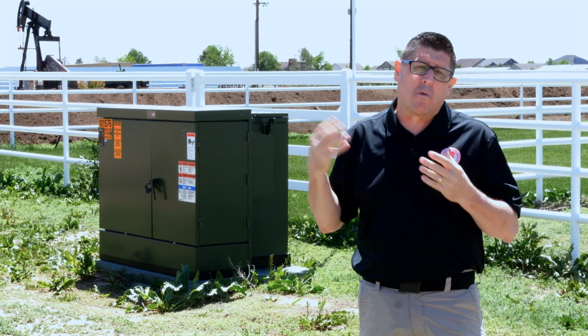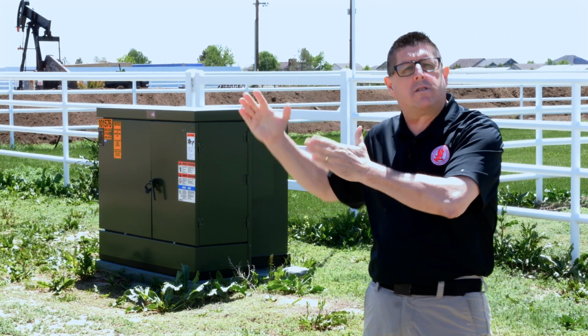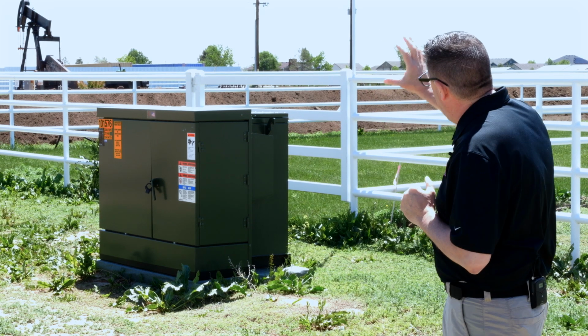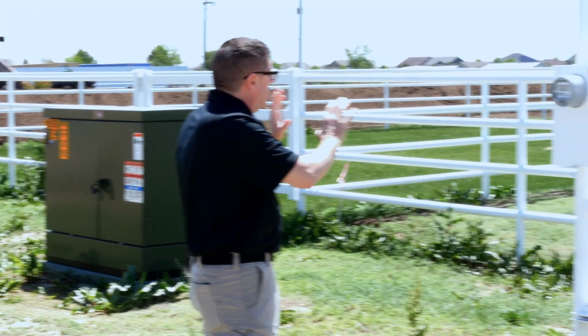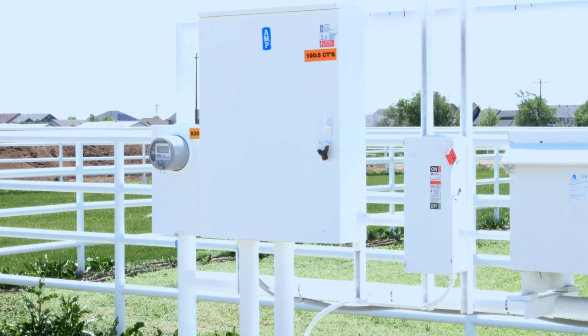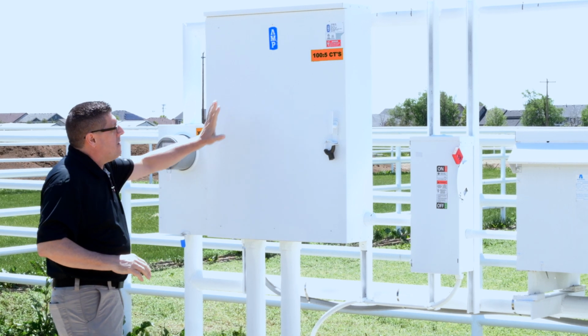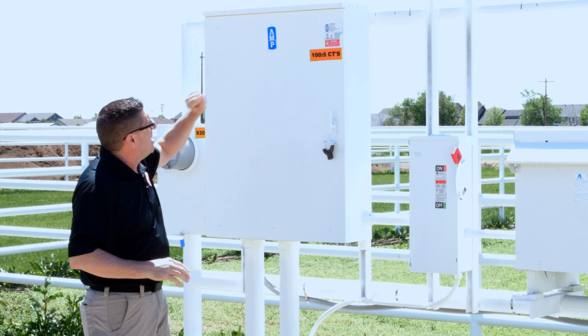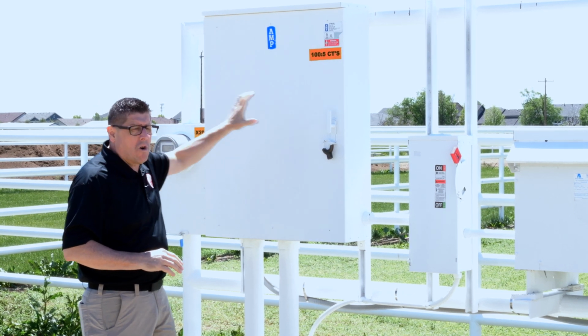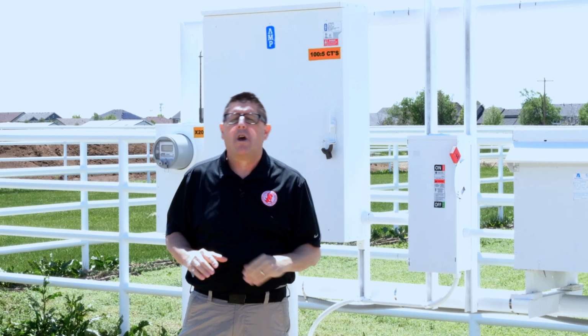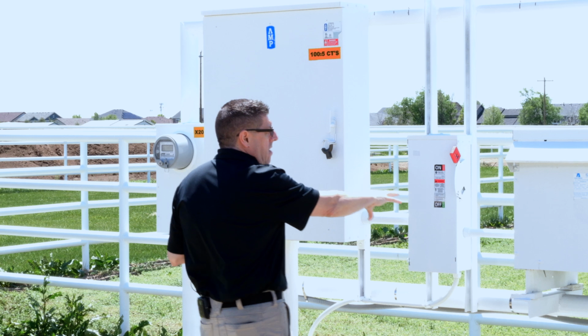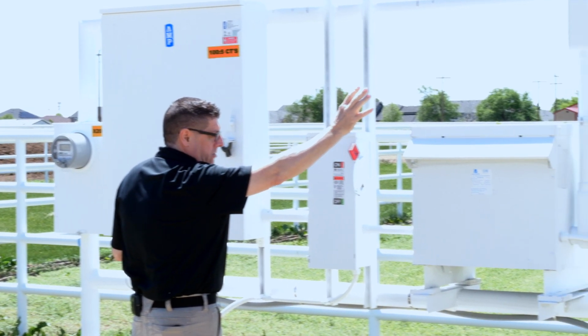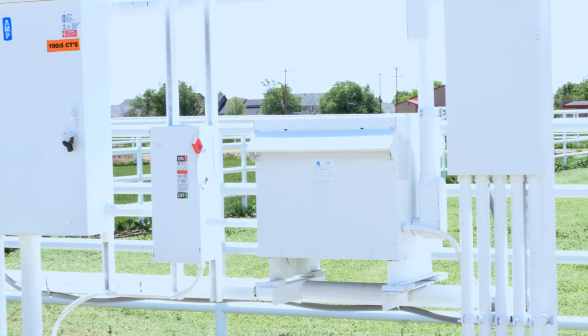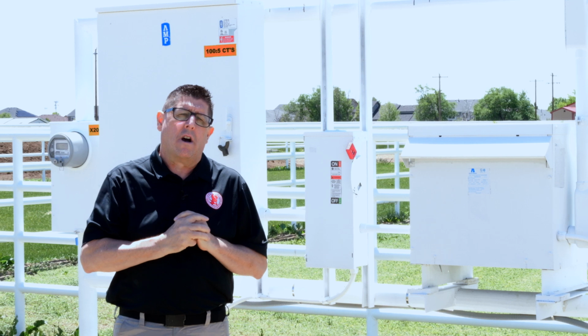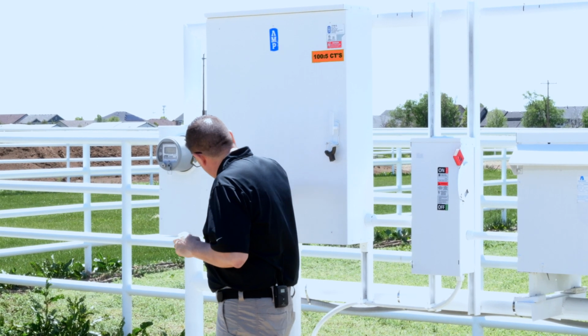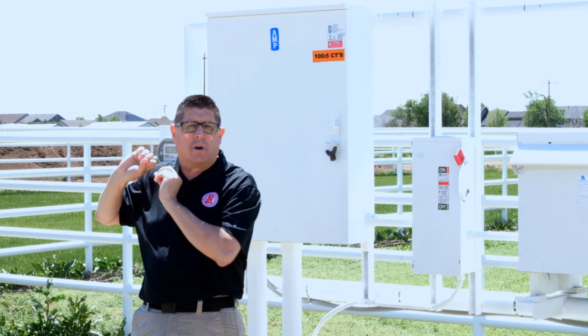But at least identifying where that service is coming from will help you identify how things maneuver and migrate through the property. So we go from that utility to over my left shoulder to where all of this distribution is located. We've got a meter socket here. We've got a utility CT panel here. This is rated at 600 volts, 400 amps, and then this is being distributed through the rest of the campus. We've got a disconnect here, a transformer here, and we've got a service disconnect panel here. All of those are going to buildings that we have located on that side of the property. And then we have from here the conduit coming out, and that's what's going to the building we just inspected.